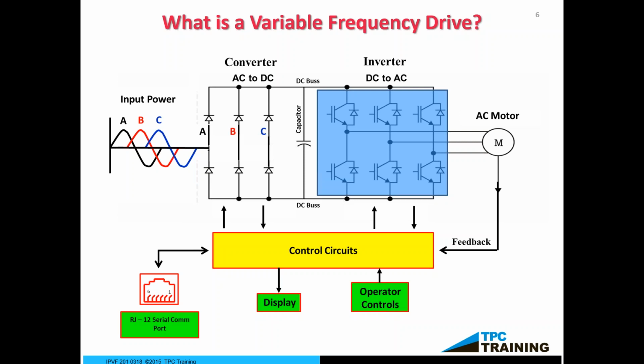This is your drive. We got AC, converts it to DC, and that DC back to that pulse width modulated signal. And if you look close at this circuit here, if you replace that capacitor that you see in the center there with batteries, for example, it would really look like a UPS system, doesn't it? If you replace that capacitor with solar panels, it could be a solar system. This particular circuit is a very, very common circuit in the power industry, whether it's variable frequency drives, UPS system, or a solar photovoltaic system. So this is a very, very common system. I ask that you write it down. You're going to see it again, whether it be in the drive world, or whether it be in the UPS world, or whether it be in the solar photovoltaic world.